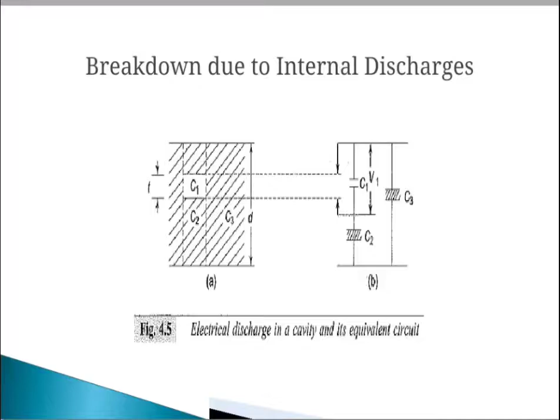When voltage V is applied, V1 reaches the breakdown strength of the medium in the cavity and breakdown occurs. This V1 is called the discharge inception voltage. When the applied voltage is AC, breakdown occurs in both half cycles, and the number of discharges will depend on the applied voltage. The voltage and the discharge current waveform are shown in the image.